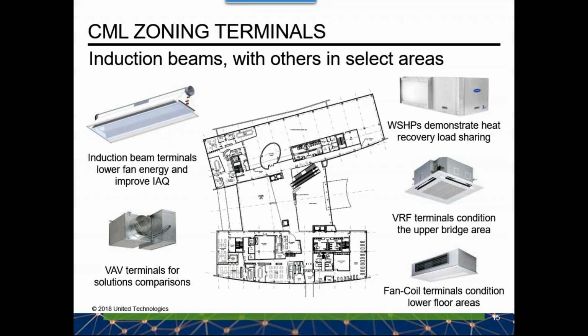On the staff floors, we've got about 400 induction terminals. We're getting the required 40 CFM per person, probably more when you look at a diversified number, because any day at work, never is everybody there. I'd say the diversity on this building is proving out to be as low as maybe 0.7, so 30% of the people with assigned desks or rooms do not come into work on any given day.